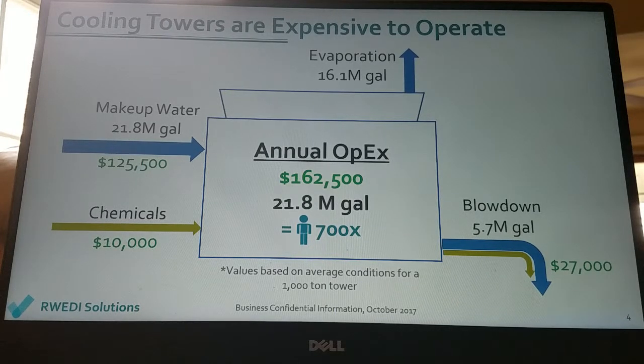The industry predominantly uses chemicals provided by water treatment service companies to manage scaling, corrosion, and biological fouling in these cooling towers. The chemical treatment offers limited ability to conserve water by increasing the amount of chemicals added to the system. However, the increased cost of chemicals is offset by any reduction in water expenses. Chemical addition is also labor-intensive, requiring 2 to 3 site visits per week by the service company. There are a few niche technologies available in the market to replace chemical treatment, but these technologies have not received widespread adoption due to their limited field of use and practical performance limitations.